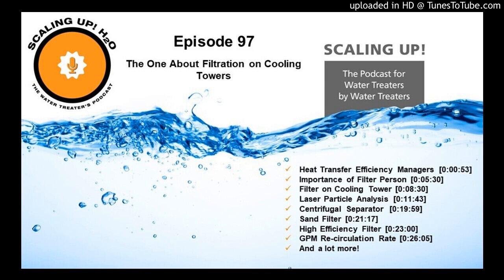The problem is that they're the least expensive way for a customer to feel like he's removing particulate from his cooling system. But those particles are settling in the sump normally, and the sump is actually the design in the cooling tower. It's a design for stagnant water below the cooling tower so that the heavy particles will settle in the sump and don't get blown around through the system and onto heat transfer surfaces. So the centrifugal separator is not ideal for a water treater. That's not going to improve your water treatment program.